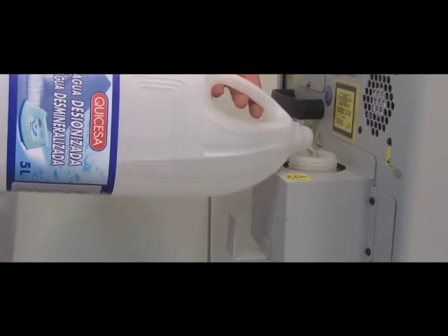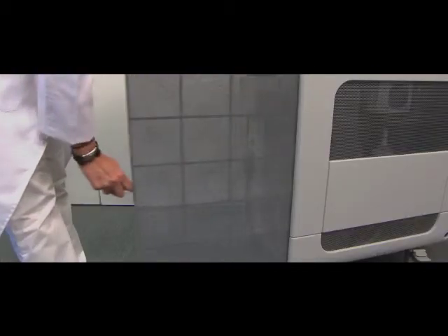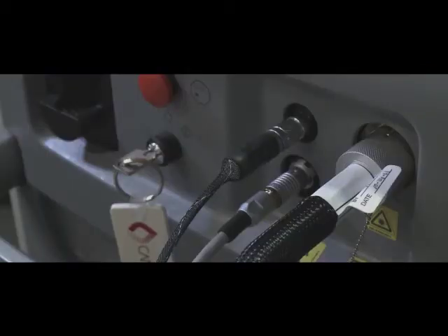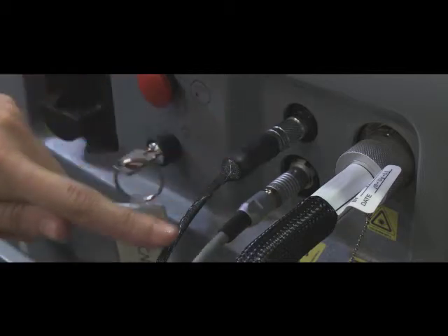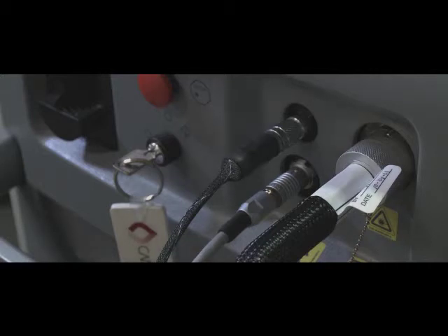The water canister should only be filled with distilled or deionized water and should be checked weekly. The back filter is easily removed and cleaned with a vacuum or canned air once per week. The delivery system consists of the electrical cord, the Cryogen line, and the optical fiber. It must be handled at all times with extreme care. Make sure the cables are hung and not on the floor.